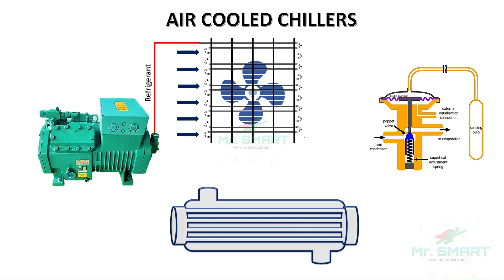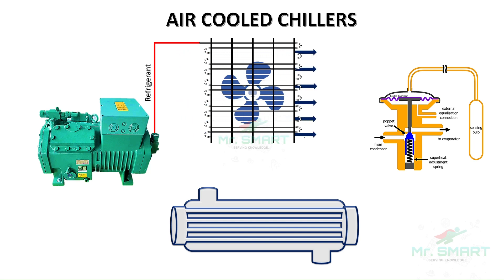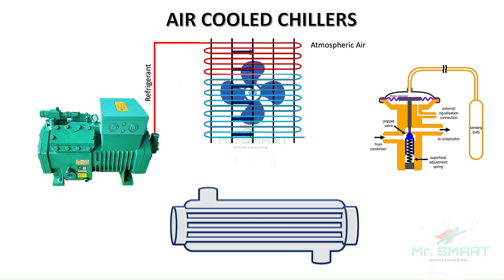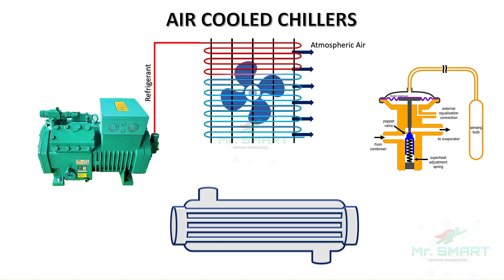During operation, the low-pressure refrigerant is compressed into a high-pressure, high-temperature refrigerant by the compressor and passed through the condenser. At the condenser, the high-pressure refrigerant releases heat to the surrounding air, cooling down and condensing into a high-pressure liquid. In an air-cooled chiller, fans help move ambient atmospheric air over the condenser coils to dissipate heat.